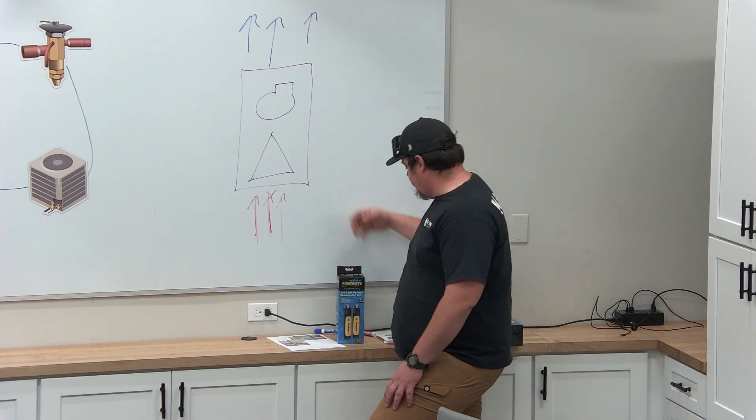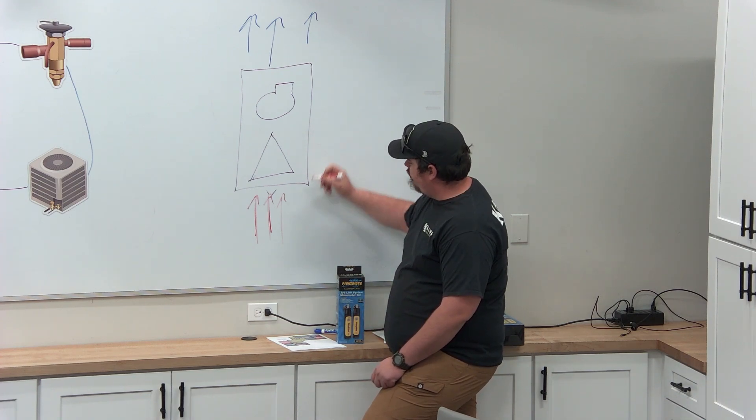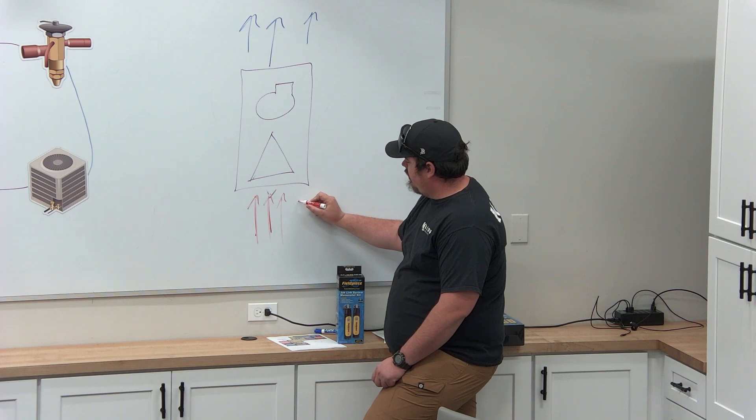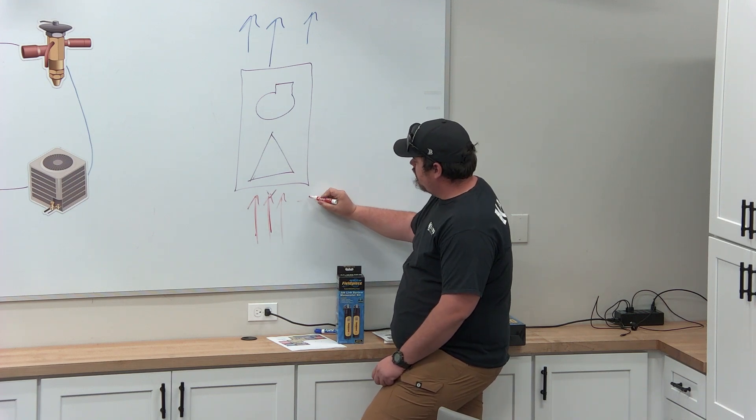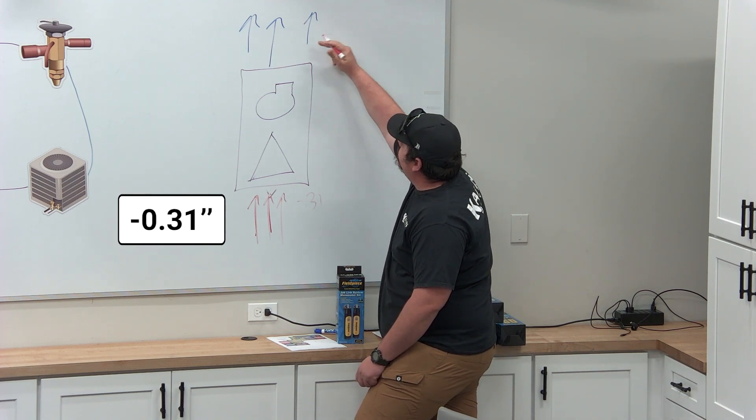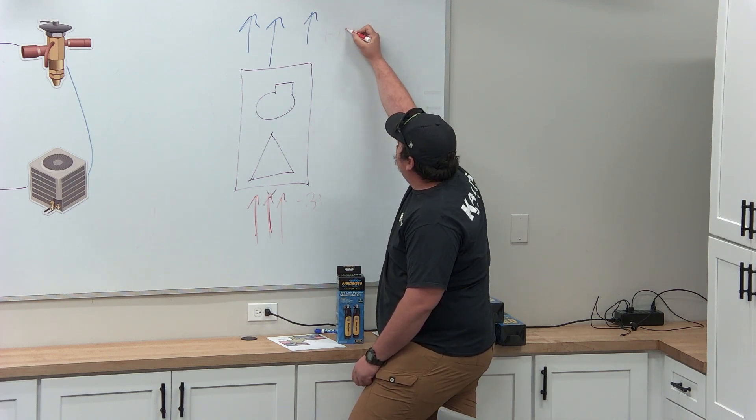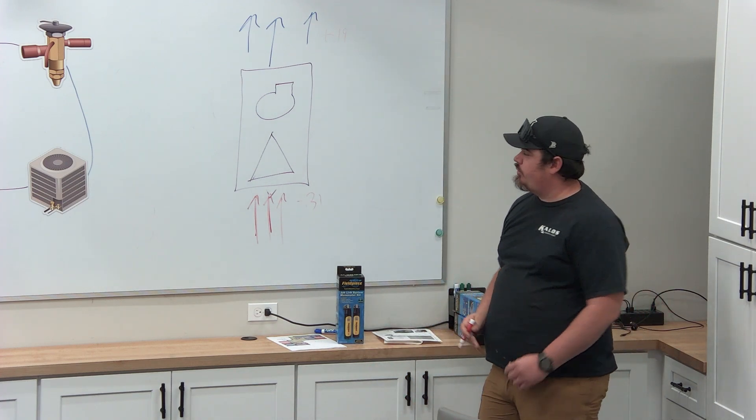So if we say that this system right now at a 5-ton and it's rated for a 0.5, and we have minus, because your minus will be here because it's sucking through, so minus 0.31, and then we have a positive because we're throwing air, 0.19, that's going to give us that 0.5, if that's in a perfect world where we're at.